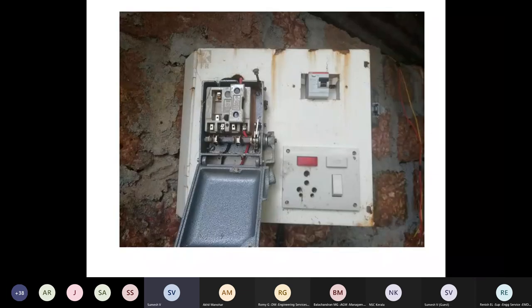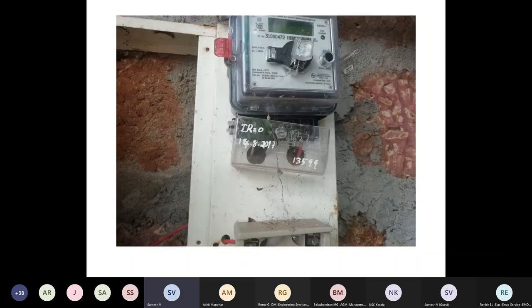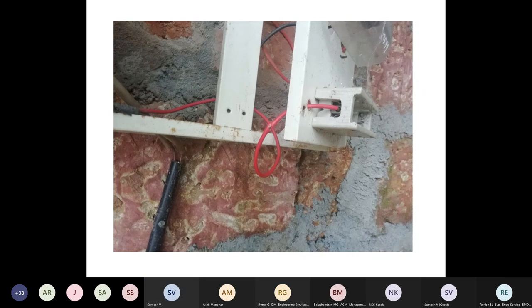In connection with the inquiry of this accident, we see that this is the metering box provided at the installation. Here, the main switch and RCCB are provided on a hinged door. On the other side, on another hinged door, the meter and cutout fuses are provided. We noticed that the wire connected to the cutout fuse is damaged due to pressing with the sharp edge of the metal board. Each time the door of the meter board is opened, this wire gets pressed with the metal frame, and the insulation is damaged. Thus, supply appeared on the body. The body is connected to the earth electrode through an earth wire. Supply appeared in the earth wire, and the fox came across that earth wire and got electrocuted.